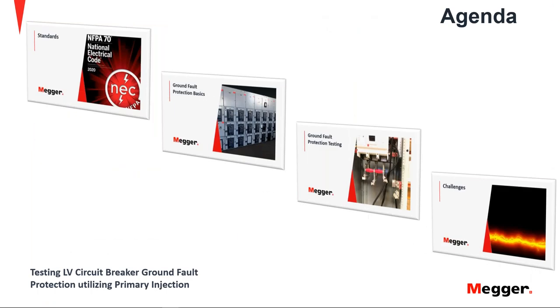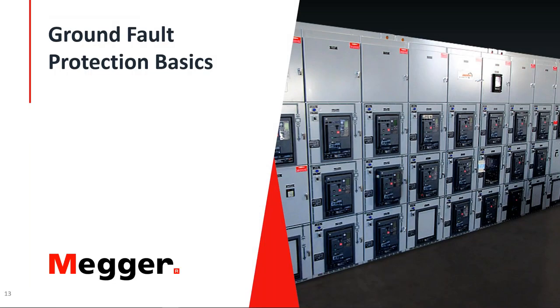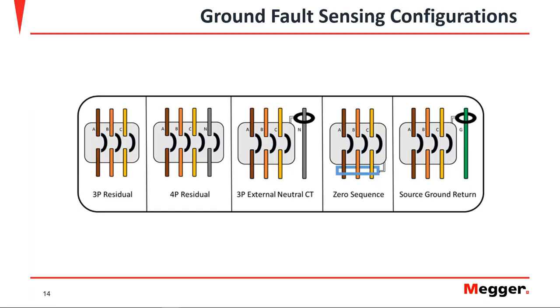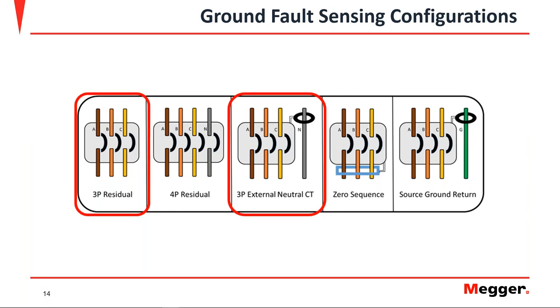Now let's go to the basics of Ground Fault Protection. Our objective today is not to discuss the ground fault protection scheme itself, but to make sure we're on the same page before going into testing. There are several different methods to detect this type of fault with our circuit breaker. We have the residual sense configuration — either 3-pole or 4-pole — the option to have an external neutral CT, the zero sequence, and the source ground return.